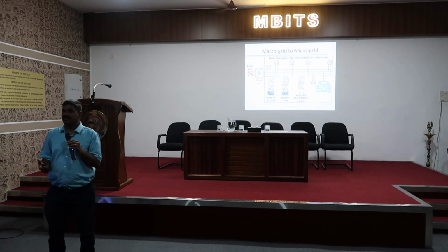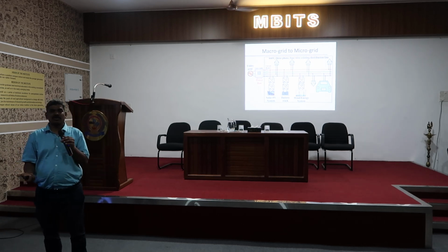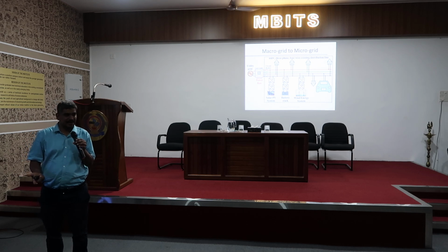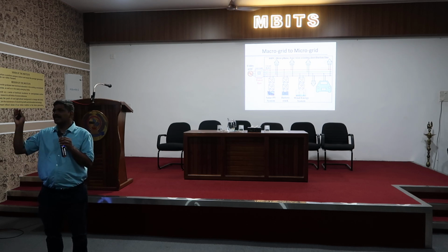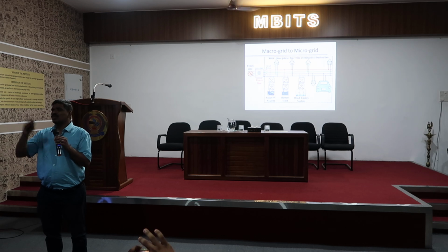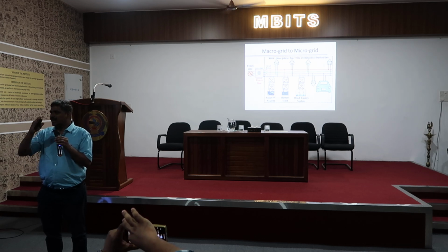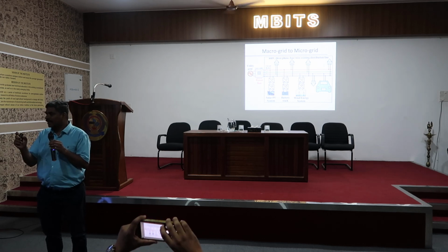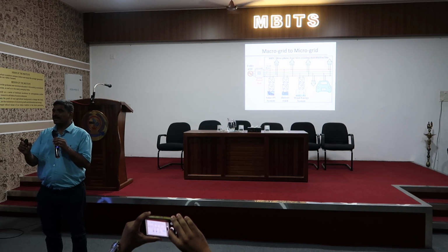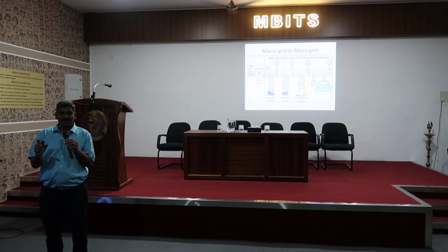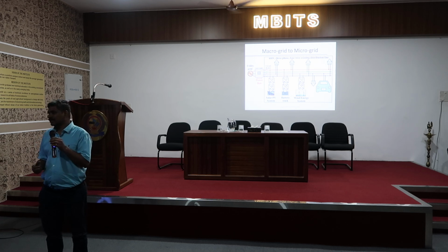Because of that, although we call the transformer efficiency 98%, the transformer efficiency degrades to sometimes 90% or less. So for a 100 kVA transformer, if you take 90% efficiency, that's 10 kilowatts of loss.